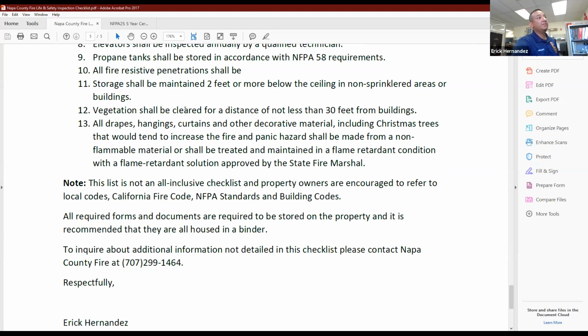Storage shall be maintained 2 feet or more below the ceiling in non-sprinklered areas in buildings. So if you have an office or any commercial building that has no sprinkler system, you're required to have a minimum distance from the ceiling of 2 feet or less. I'm sorry, 2 feet or more. So you want that open separation.